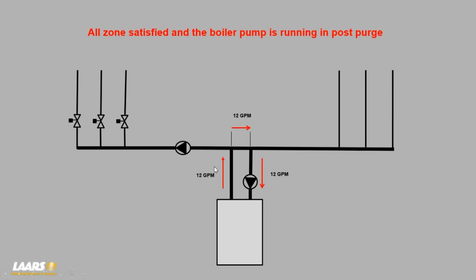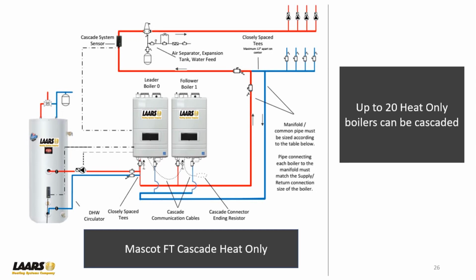And it's just going to pull that heat out of the heat exchanger so you don't trip a high limit, especially if you had a water tube design heat exchanger. Our product that we're talking about today is a fire tube design. So that is what pump post-purge is.